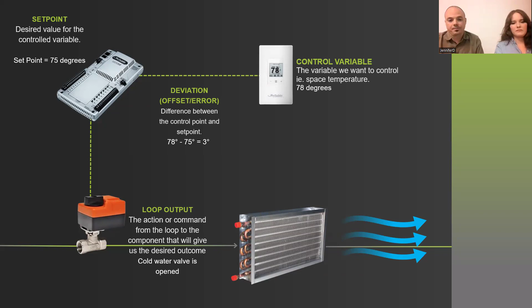One more term to throw in there is the deadband. Let's say in this example that we're not at 78 degrees, we're at 75.1 degrees. I don't necessarily need to start opening up my chilled water valve. That's where the deadband comes in. This is especially useful for maintaining the life of your systems and smoothing out the edges of how this device works. Let's say the deadband for this situation was set at 2 degrees. That's going to be a bidirectional function, so whatever our set point is, the deadband is plus or minus 1 degree to achieve that total of 2 degrees.